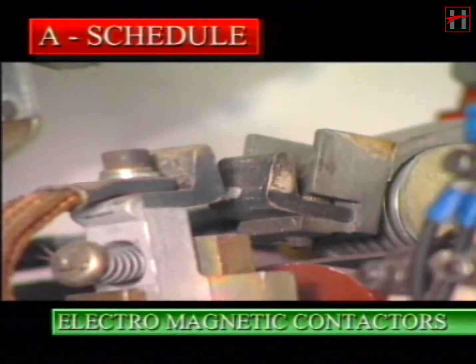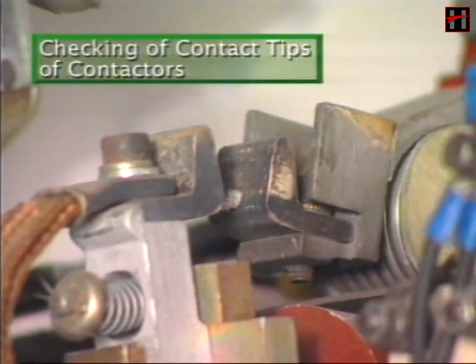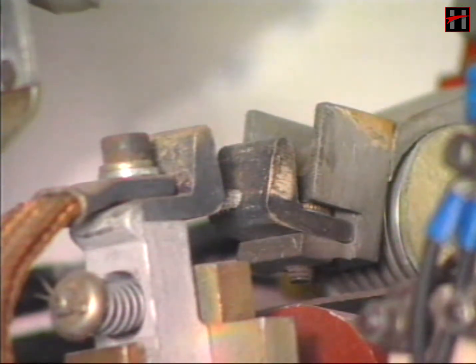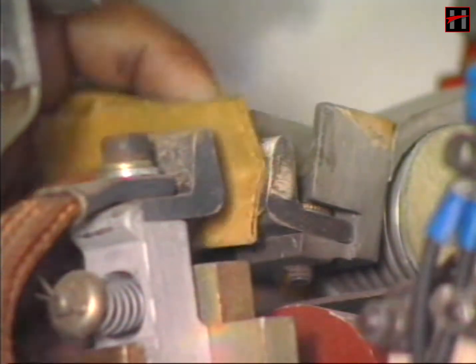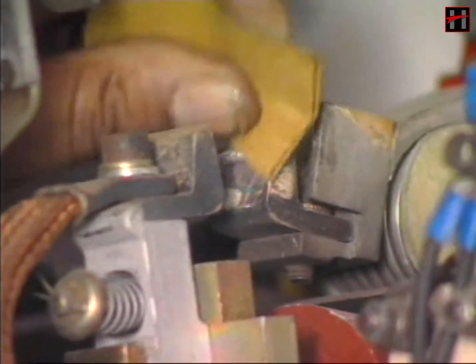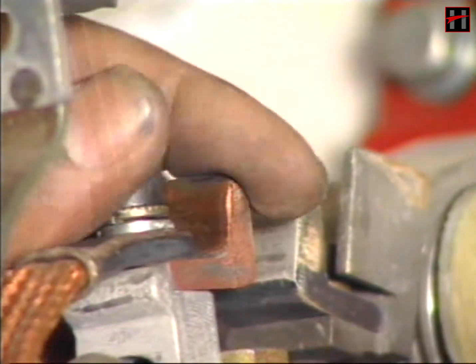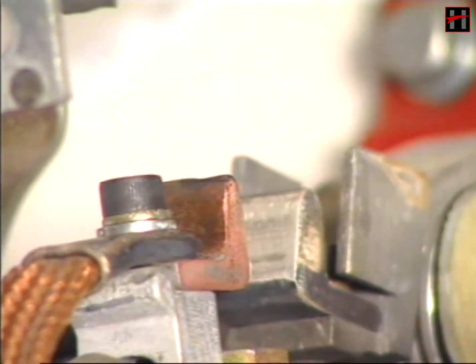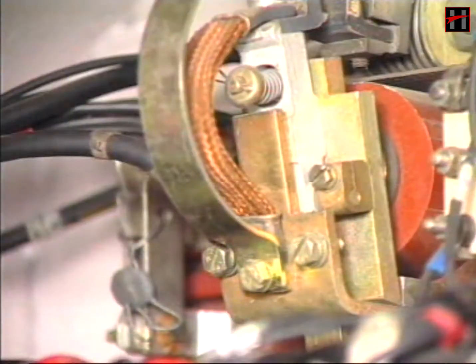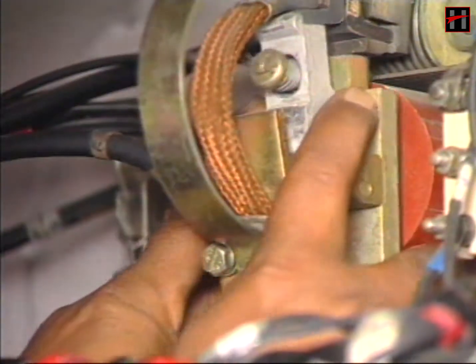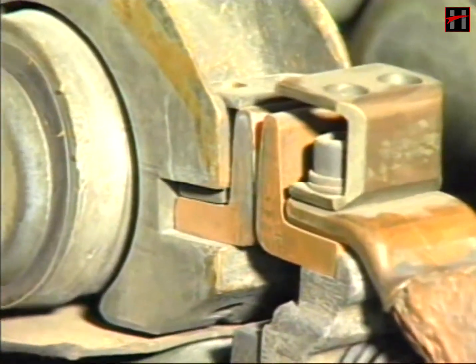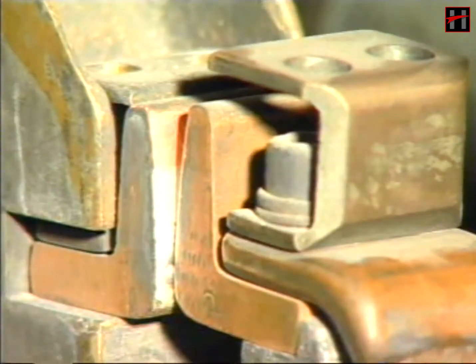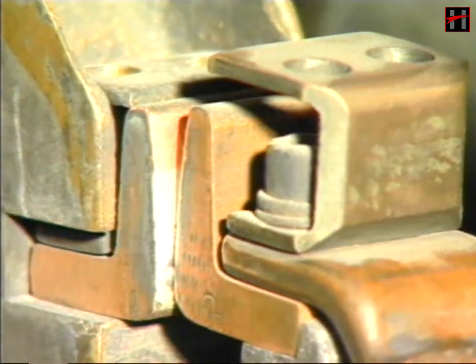In the A schedule of the electromagnetic contactors, check the contact tips of the contactors. If there is any carbonization or flash marks on the contact tips, clean the tips with clean cloth or emery paper. In case of heavy flash mark on the tips, or if the tip has worn out, replace with a new tip and ensure proper matching of the tips. Ensure free movement of the movable contact. Check the alignment and the gap between the movable contact and its fixed contact. If the alignment is not proper, rectify the fault.